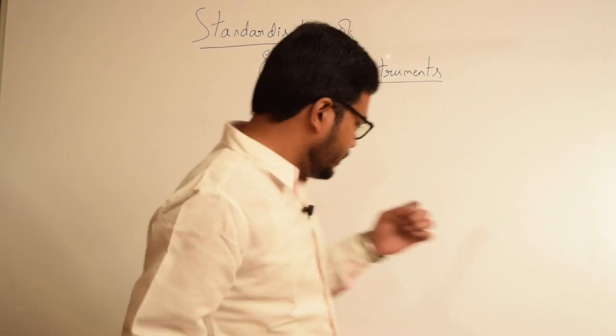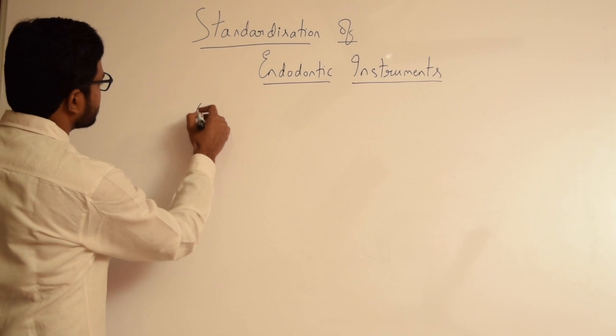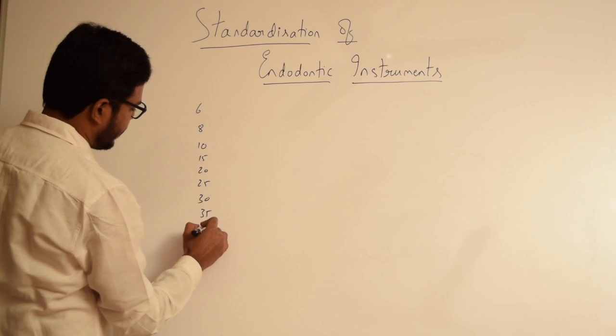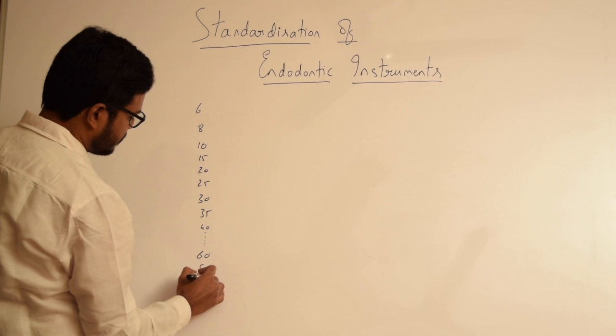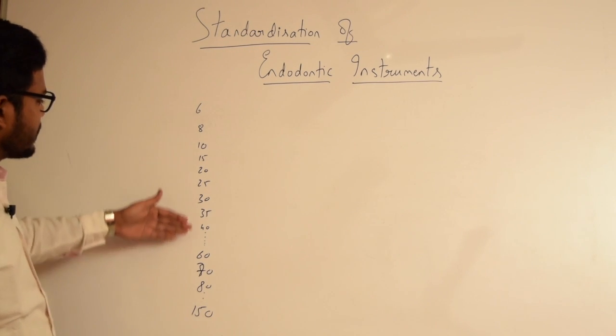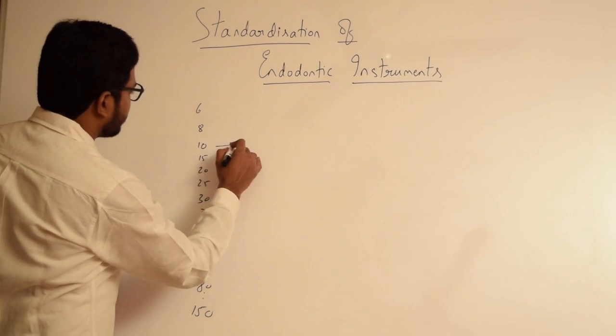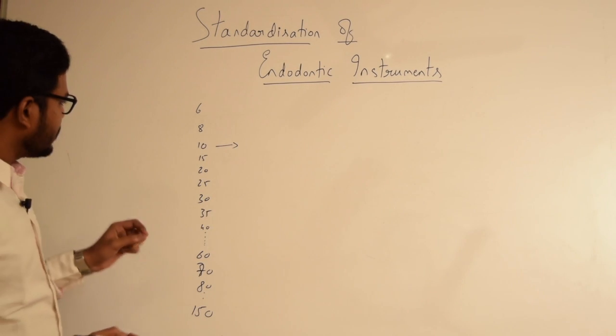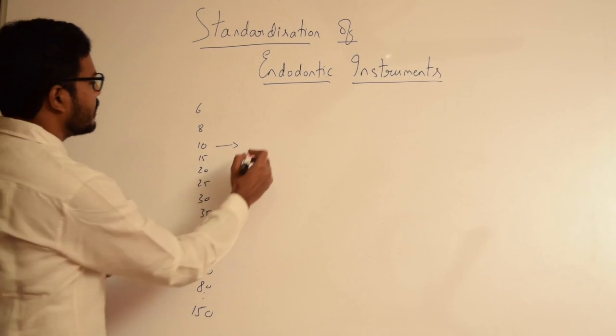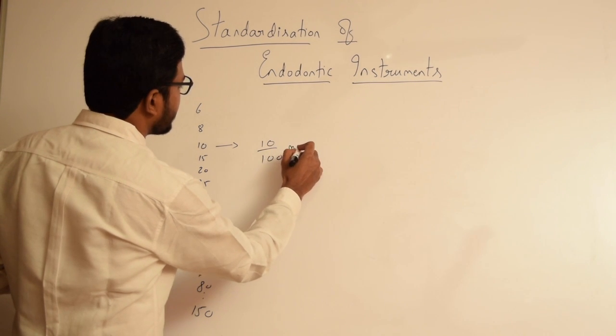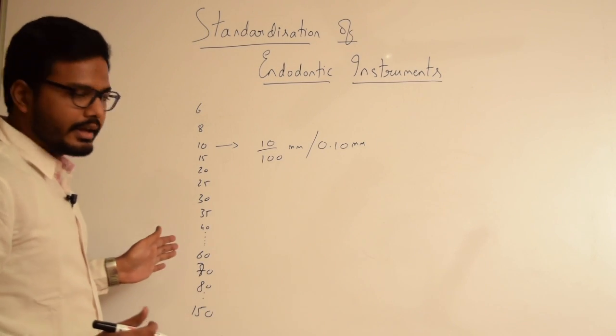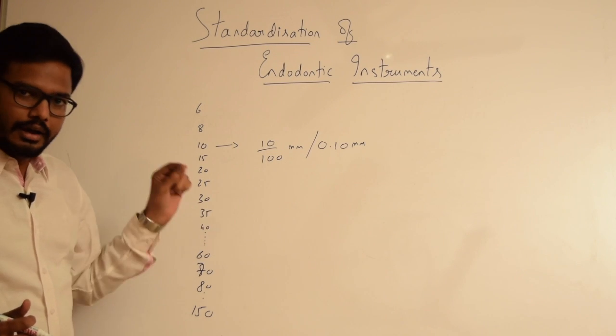The first recommendation: instruments are numbered starting from 6, 8, 10, 15, 20, 25, 30, 35, 40, and so on up to 60, 70, 80, till 150. When I say a size 10, it indicates the diameter of the instrument at the tip in hundredths of a millimeter. So a size 10 file has a diameter of 10/100 mm, or 0.10 mm. A given number in this series indicates the diameter of that particular instrument at its tip in hundredths of a millimeter.